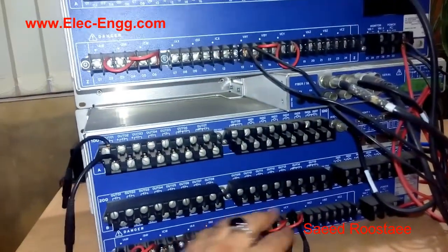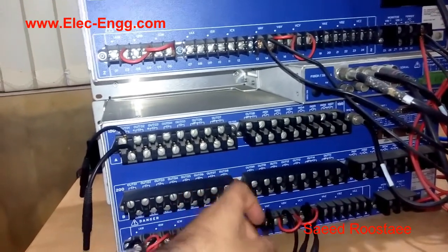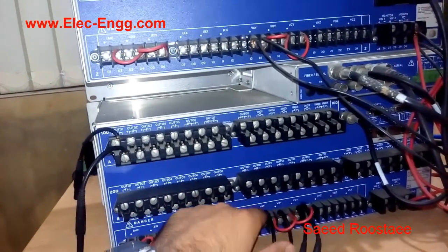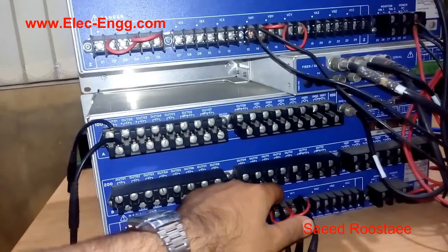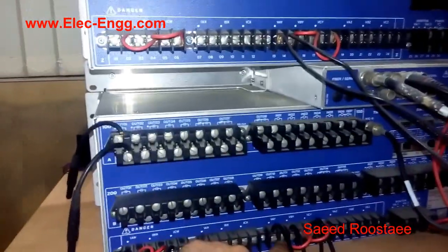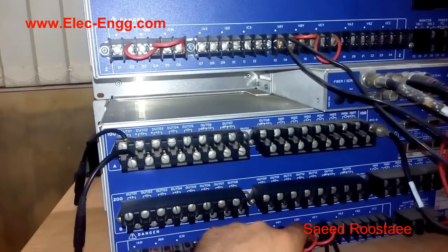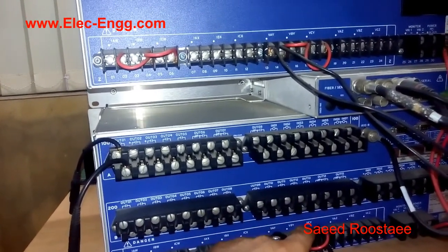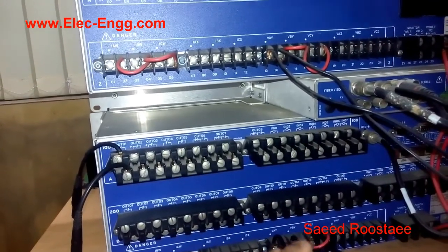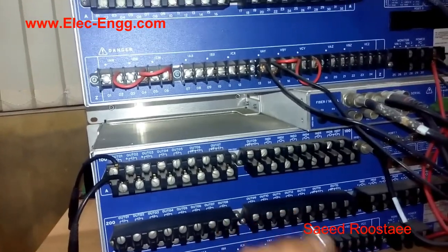The same configuration we have to do for the voltage. I connected these wires to VAY, VBY, and VCY. As you can see, there is a point here also for this pin, which is the head of the coil. So we have to connect phase 1 to this, phase 2 to VBY, and phase 3 to VCY. We also have the VAN.